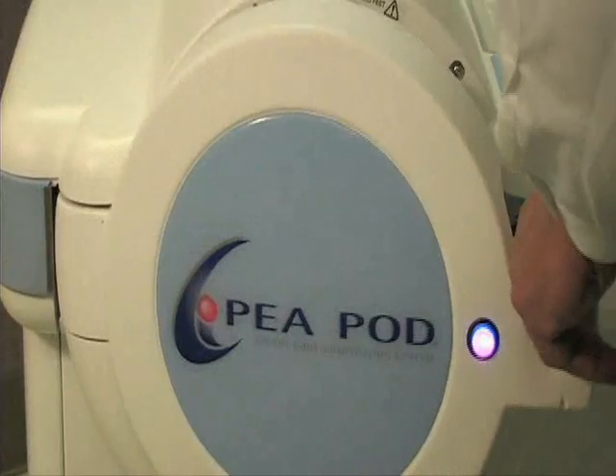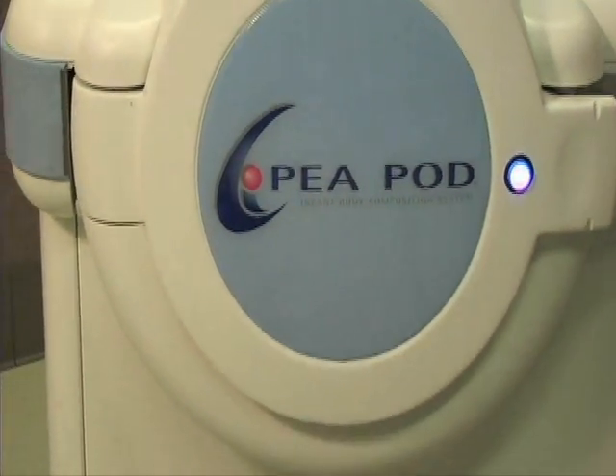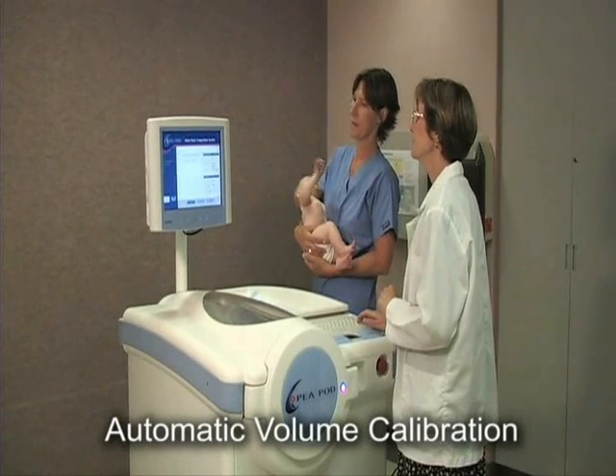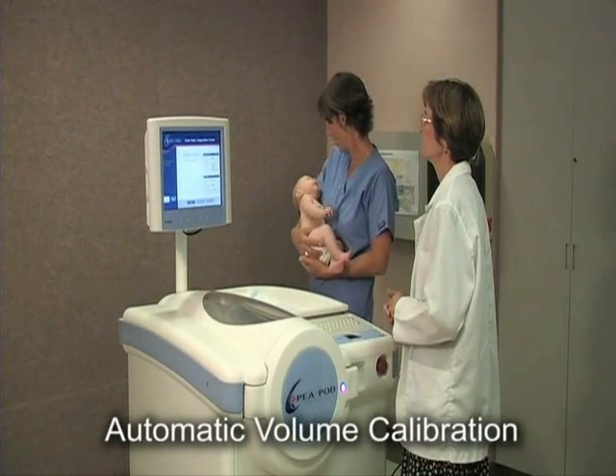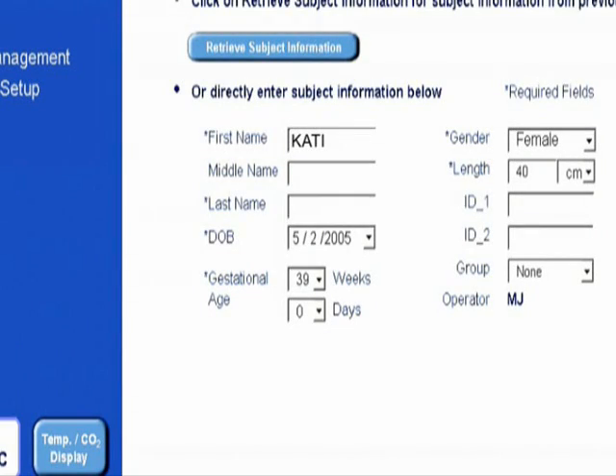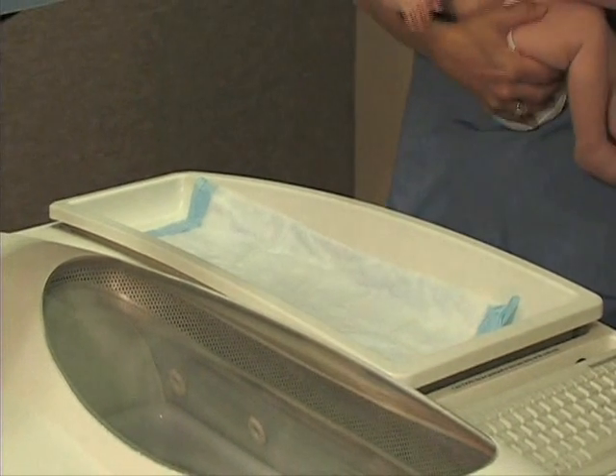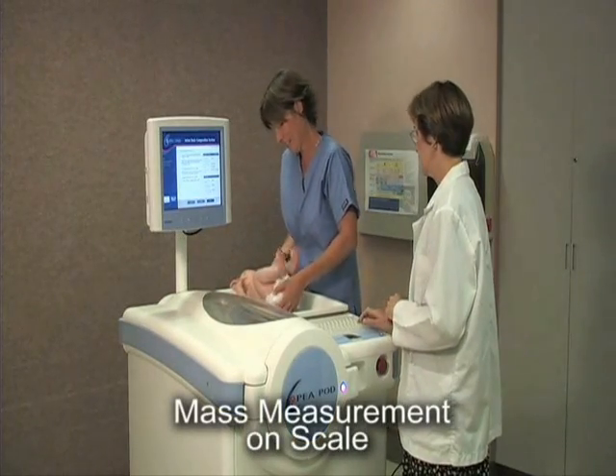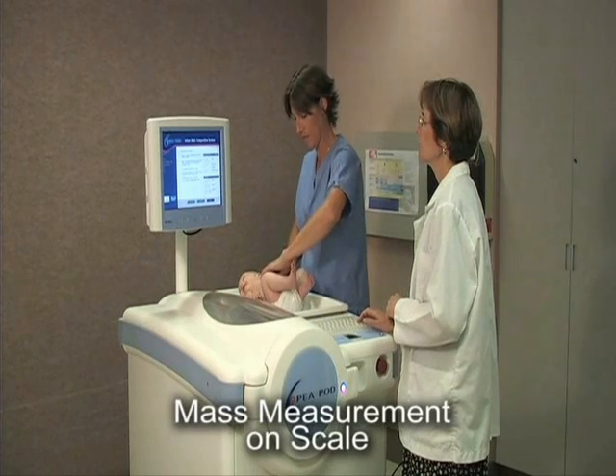The Pea Pod test process begins with a two-minute automatic volume calibration. During this calibration period, other portions of the test are performed, with screen prompts guiding the operator through each step of the test sequence. While the volume calibration is underway, basic infant information is typed into the software program or retrieved from the software if the infant has been tested previously. Next, the infant's mass is measured using the Pea Pod scale, a measurement that usually lasts between six and twenty seconds, depending on the infant's movement.